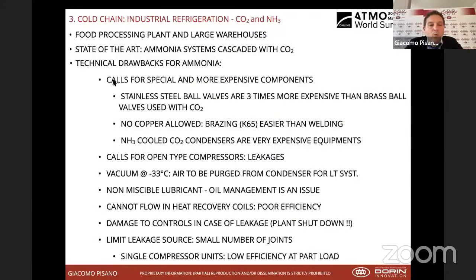When using ammonia, you normally have a cascade system, and normally you are using CO2 in the bottom part of the cycle. Therefore, CO2 and ammonia are connected through a condenser that is normally quite expensive. When dealing with ammonia, you normally work with open drive compressors, and this is a weak point from a leakage standpoint. Ammonia works in vacuum starting at minus 33, so some purgers have to be used. Ammonia works with non-miscible lubricant, so oil management is critical and is something you have to take care of very carefully.